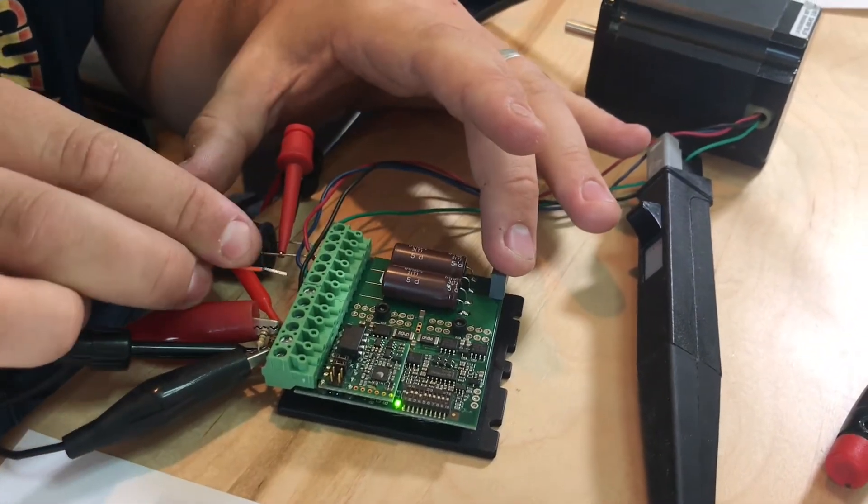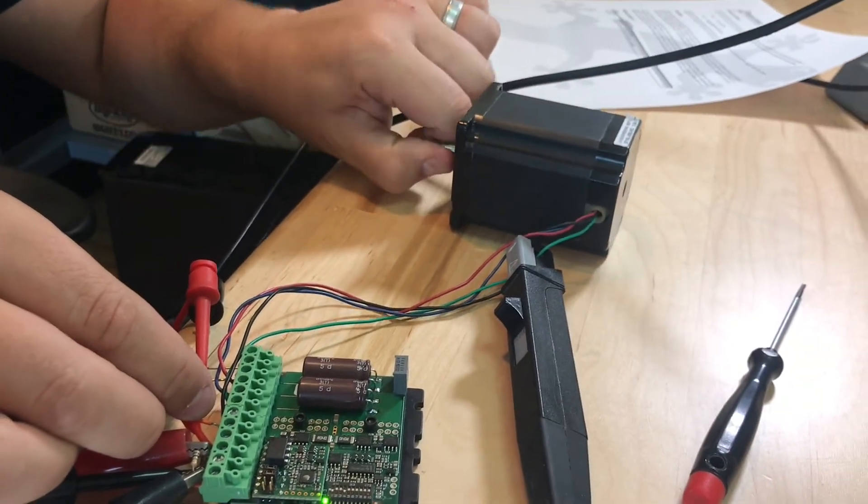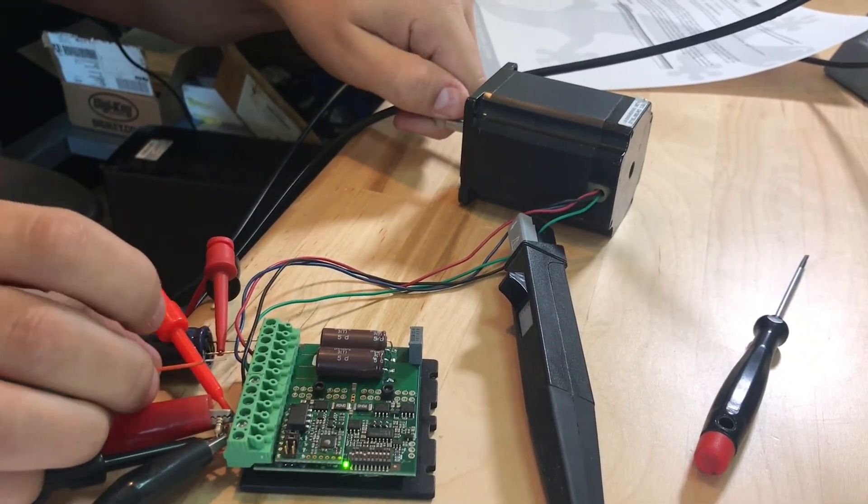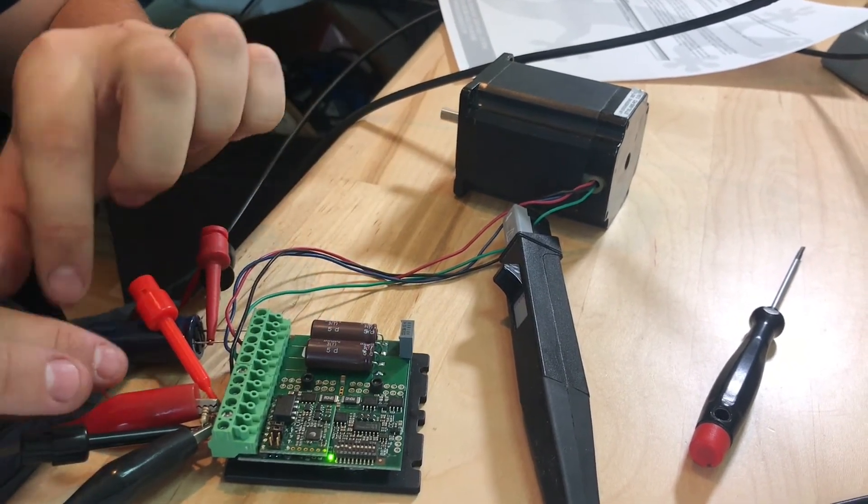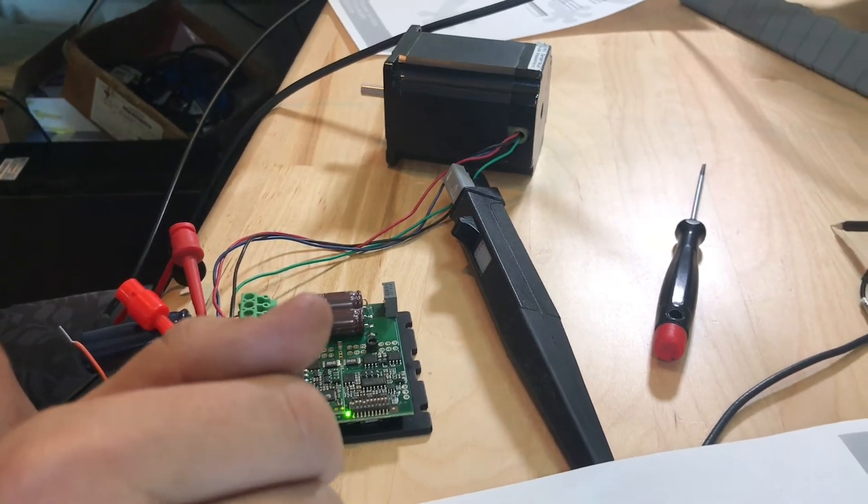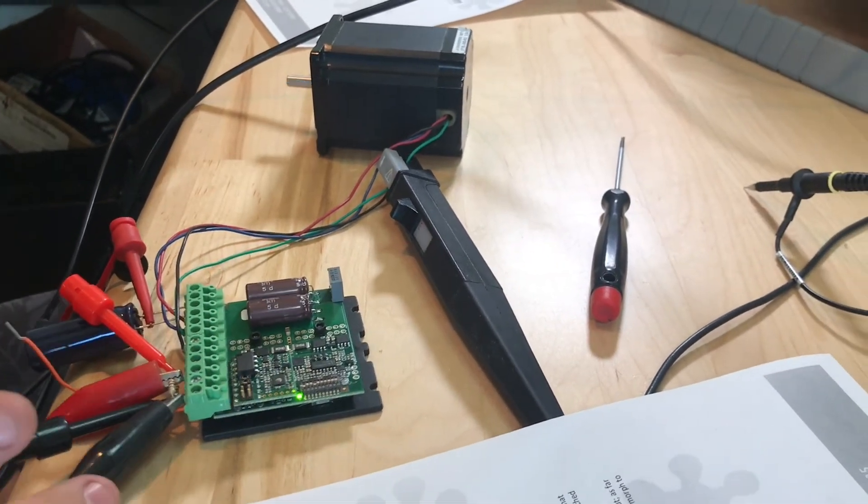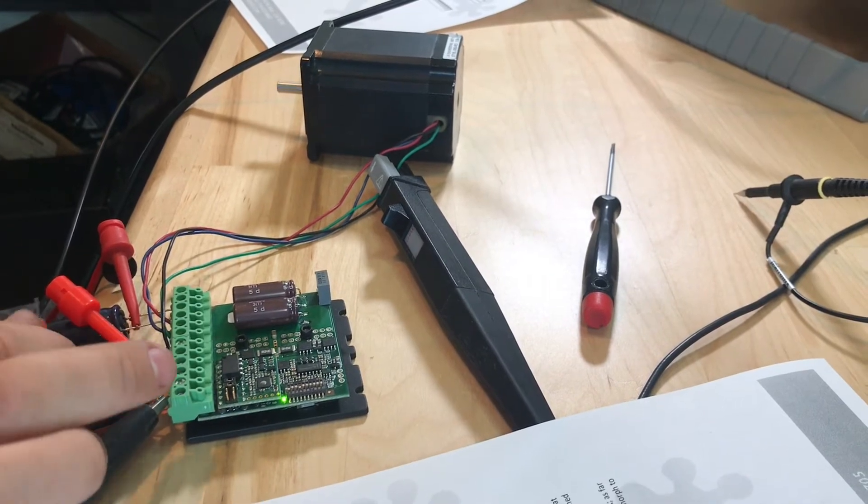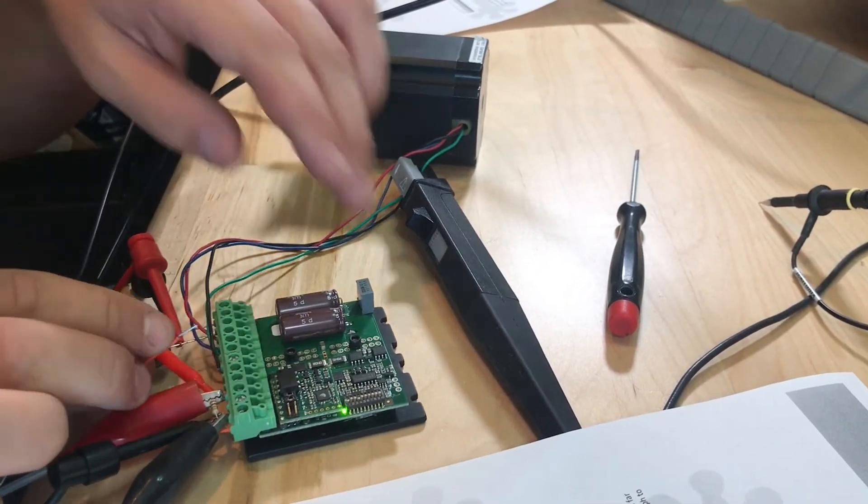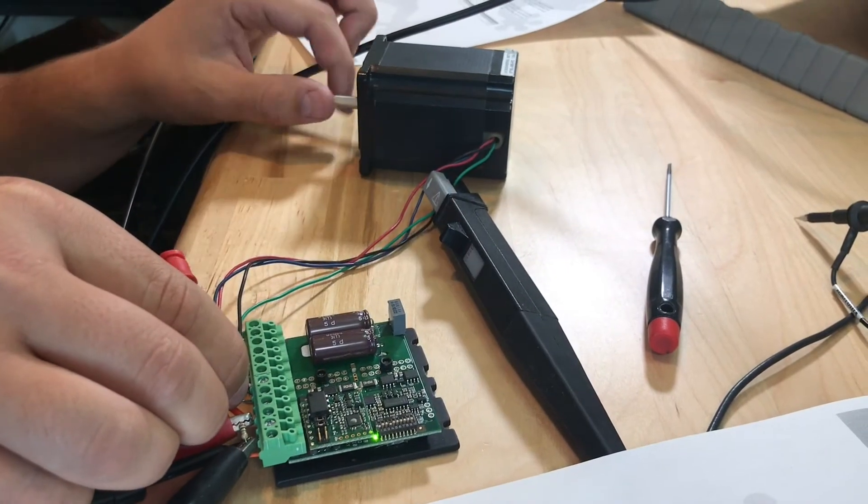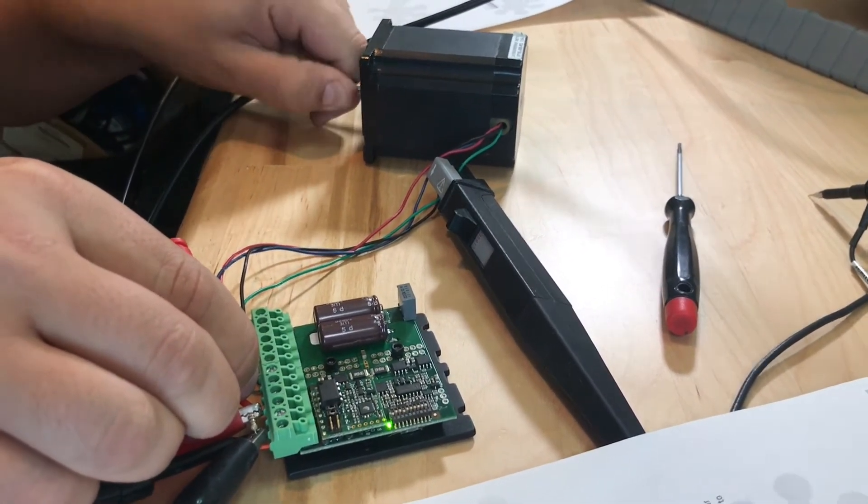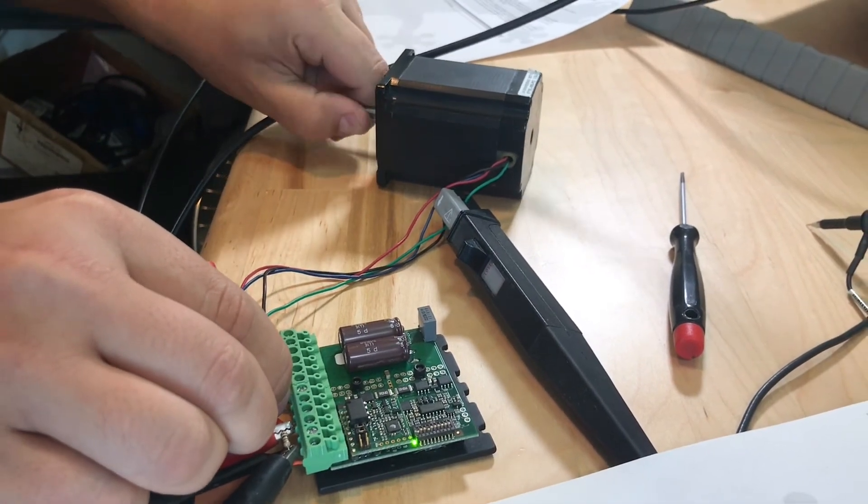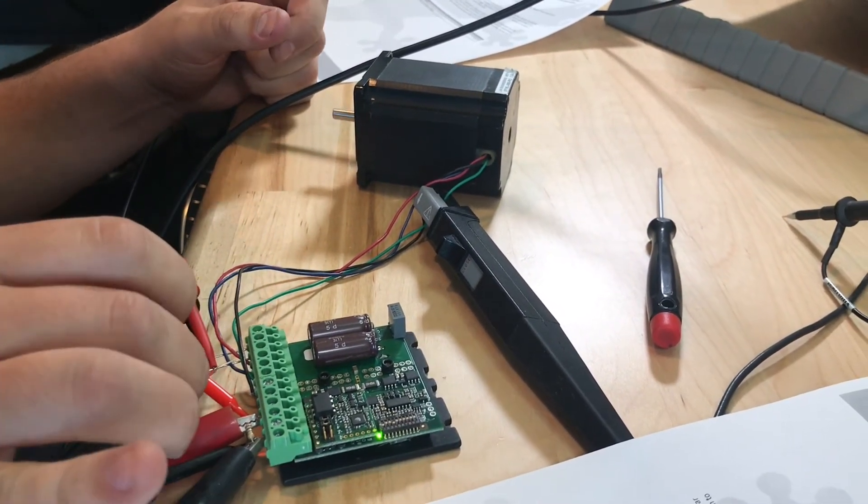So I make connection there. I can move the motor by hand. As soon as I let go, it resumes. That does not have to be connected. Generally it's connected to an emergency stop or something like that. All I have right now is just a jumper wire between 12 and 7. Every single time I make momentary contact, it will freewheel as long as that is making connection. So it would have to use a latching type switch and I remove it and it resumes.